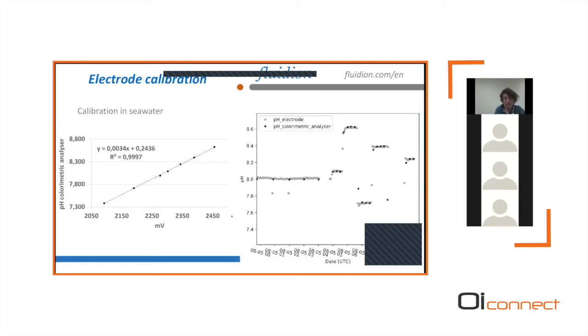Then we performed the calibration of the electrode, and this is done in seawater this time. The idea is to run in parallel the electrode and the colorimetric analyzer, and adjust the pH by adding hydrochloric acid or sodium hydroxide. And you obtain a linear response of the electrode as a function of pH.